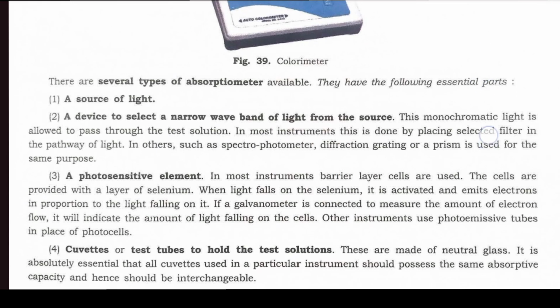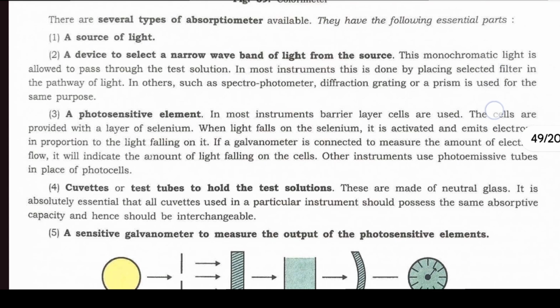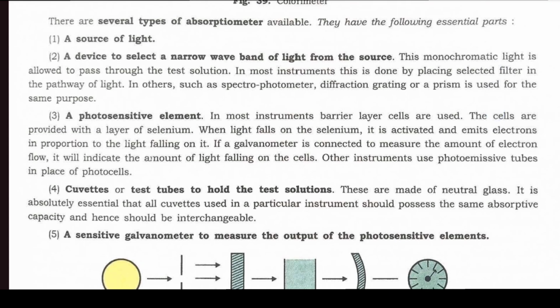There are several types of absorptiometer available. They have the following essential parts. पहला, a source of light. दूसरा, a device to select a narrow wave band of light from the source. This monochromatic light is allowed to pass through the test solution. In most instruments, this is done by placing selected filter in the pathway of light. In others, such as a spectrophotometer, diffraction grating or a prism is used for the same purpose.